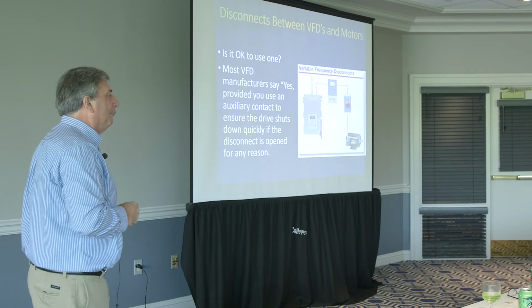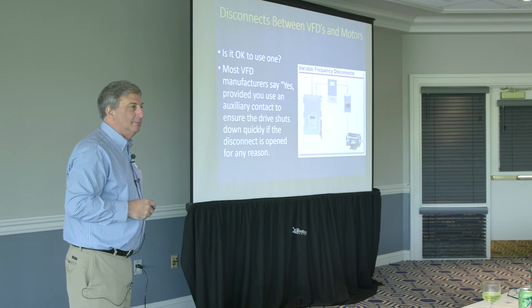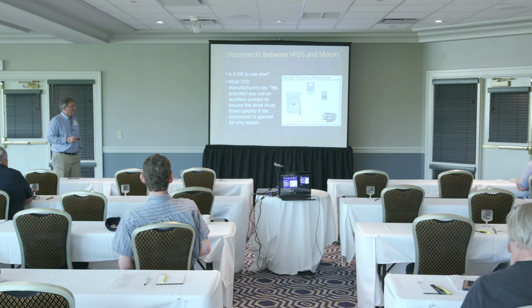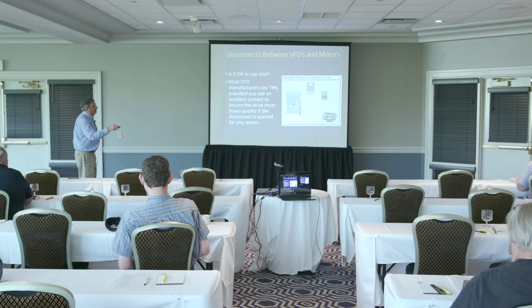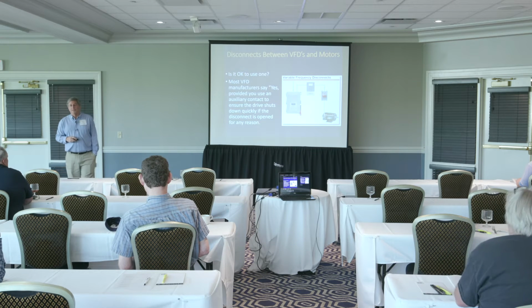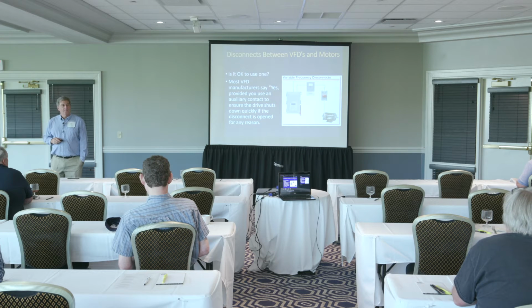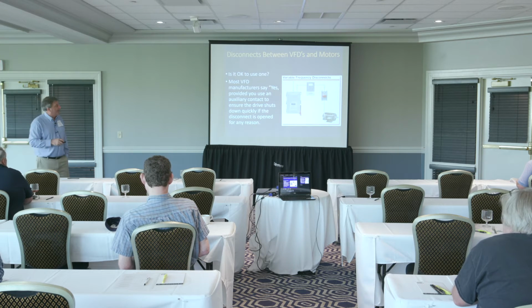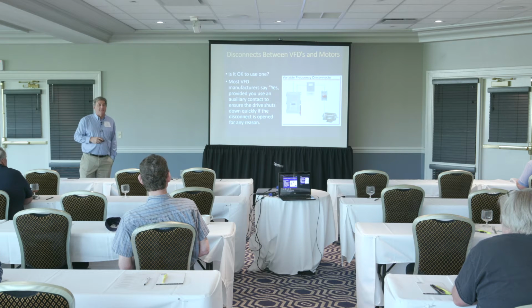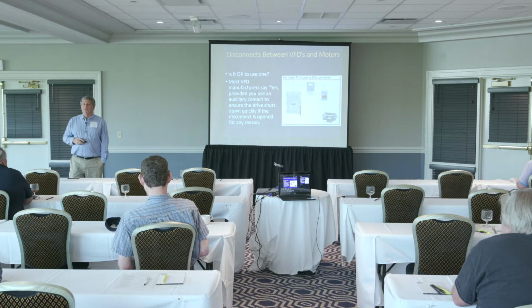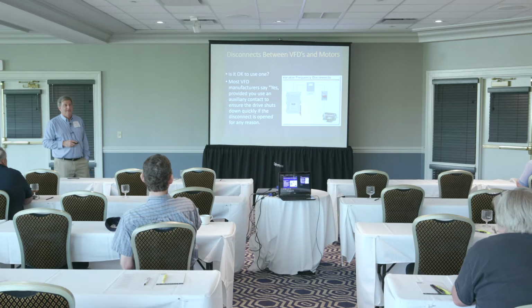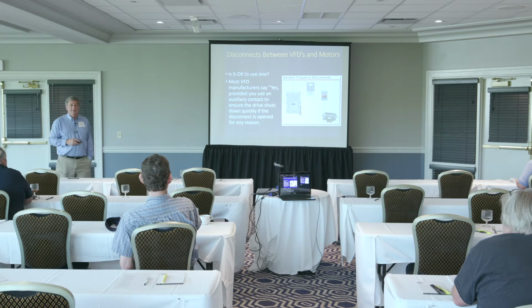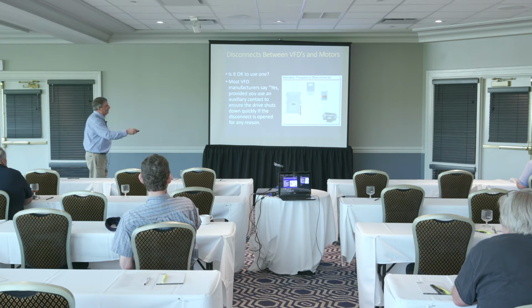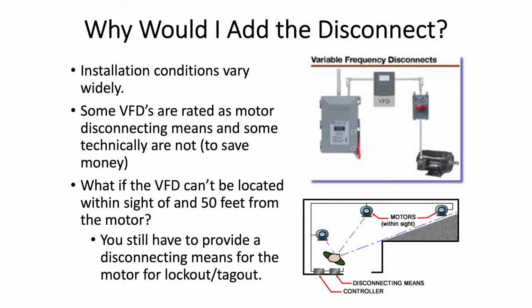I know, by the way, not only will it void the warranty, but your drive might blow up. And we're not responsible for that. And so there are various reasons. Anybody think of reasons people put that disconnect in there? Well, the common one I hear is the drive and the motor are farther than 50 feet apart. And what does the code say about a disconnect for a motor? Within sight of and within 50 feet. So now, if that's farther than 50 feet, I need a disconnect device to meet the code requirements there. Inspector said so.